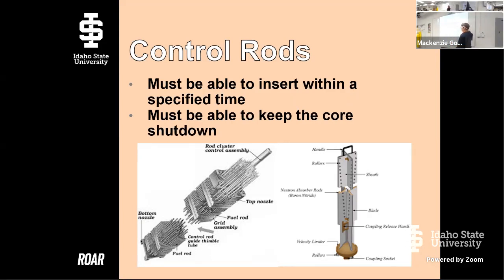This is a concept called the shutdown margin. That's how far below critical we can keep the reactor and ensure that it stays shut down. And the rods being out of the core that you have to calculate this with is called the stuck rod criterion. So not only do you have to ensure that structurally they're not going to shake out of the core with an earthquake, but physics-wise and reactor theory-wise, they have to be worth enough to keep it shut down, even if you don't have some number of them, okay?